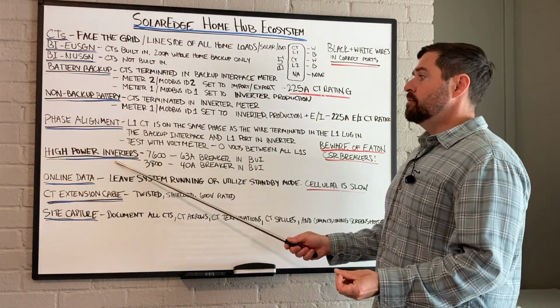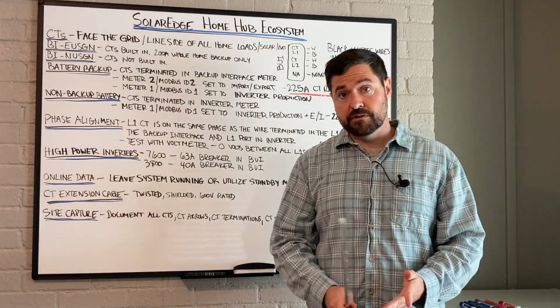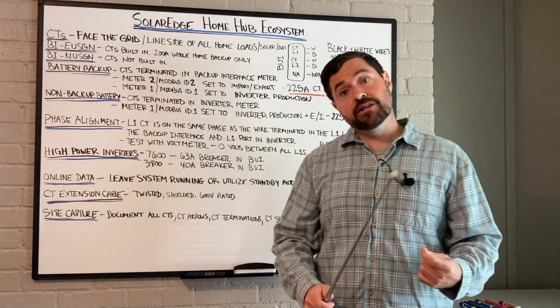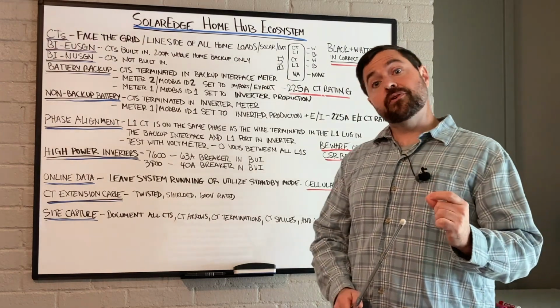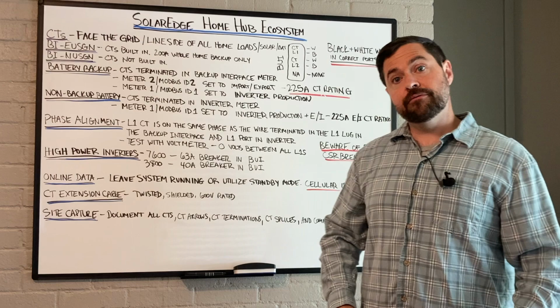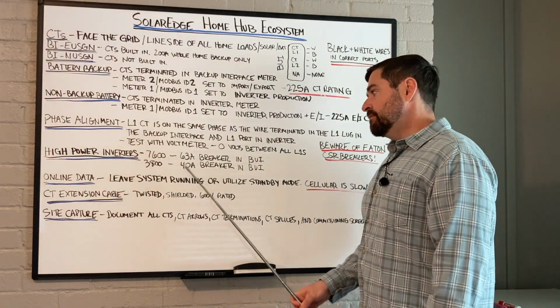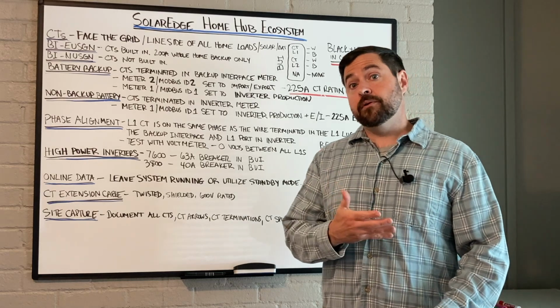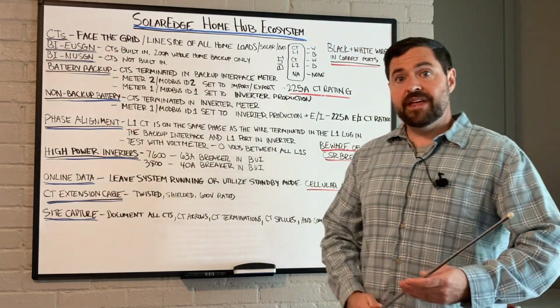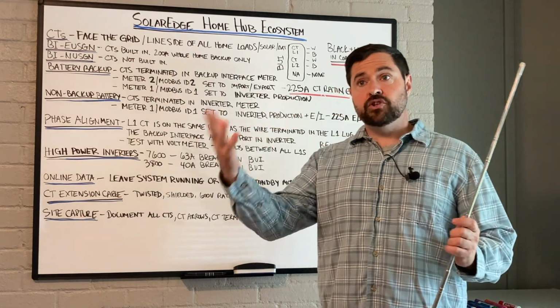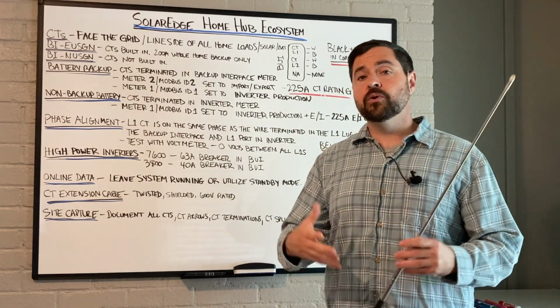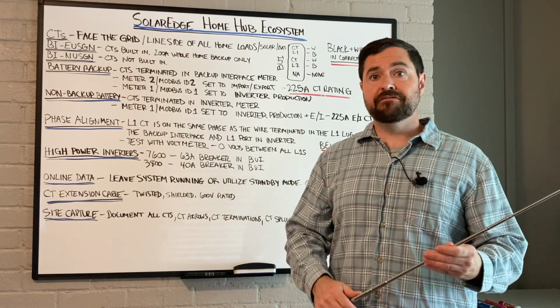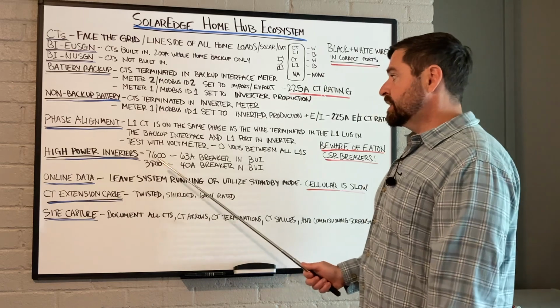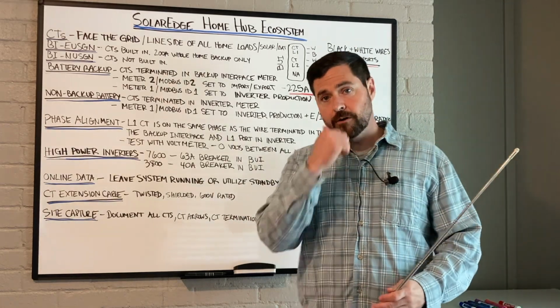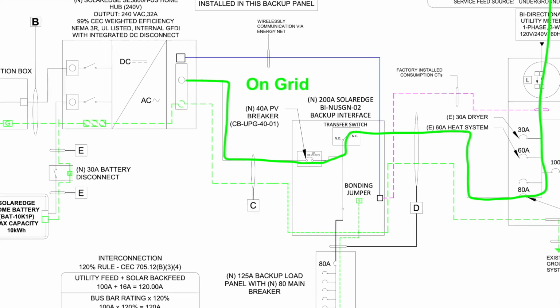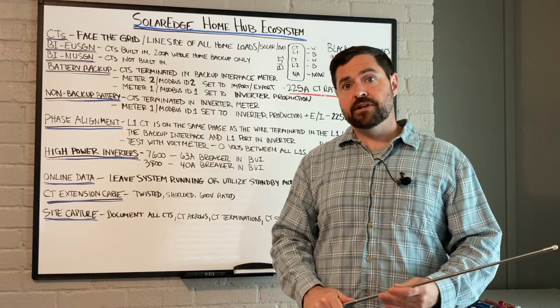Next, a very common failure point here are the high power inverters. So the high power SolarEdge energy hubs, that is going to be the 3800 watt and the 7600 watt inverter. These inverters have a higher output off-grid than they do on-grid. And the reason for that is, say you have a 200 amp service with a 200 amp main breaker, you only have 32 amps of backfeed that you can connect to that service. You can connect this 7600 watt high power inverter. The backfeed to the main service panel while it's on grid is always going to be 32 amps.